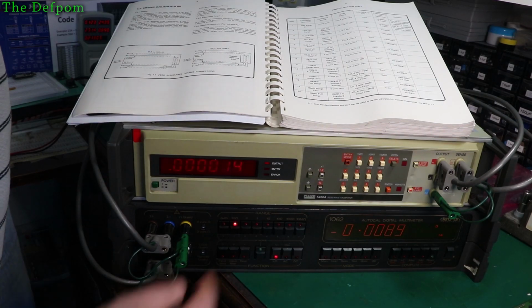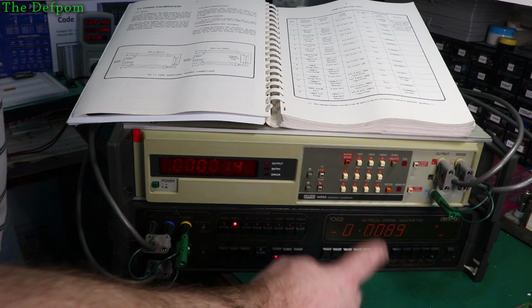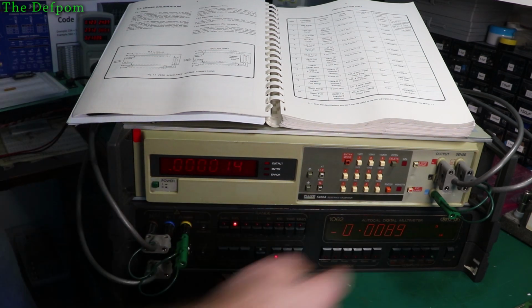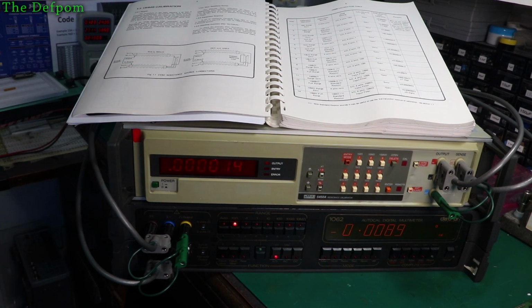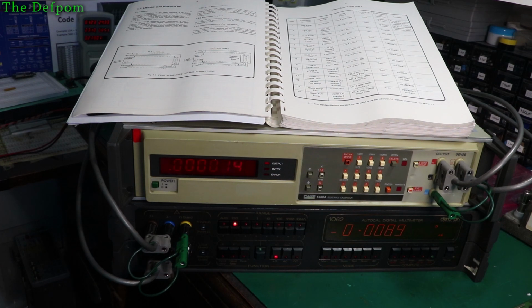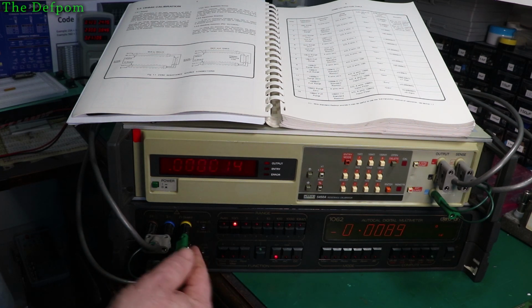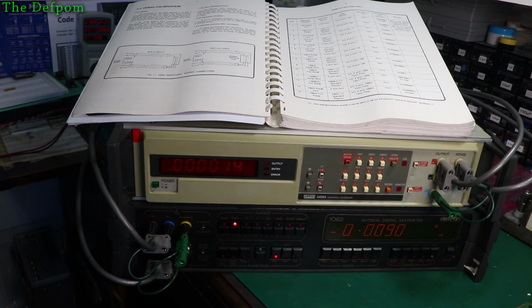So the first step is the 10 ohm range. I'll turn the calibration on, you can see by the annunciator. I've got the calibrator set to 4 wire, external guarding, local guarding, also on 4 wire. I'm using the ohms guard, using a single terminal at both ends, linked together.